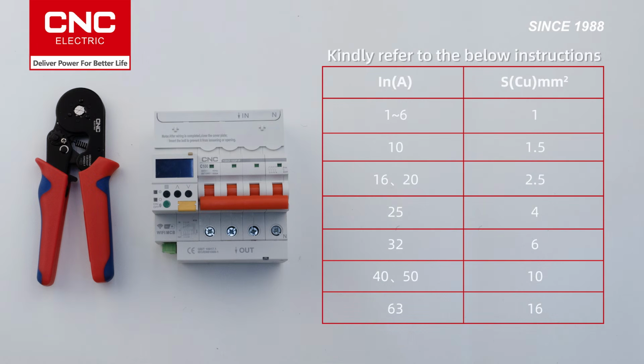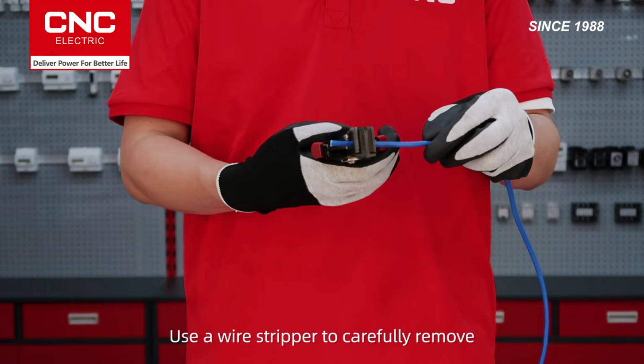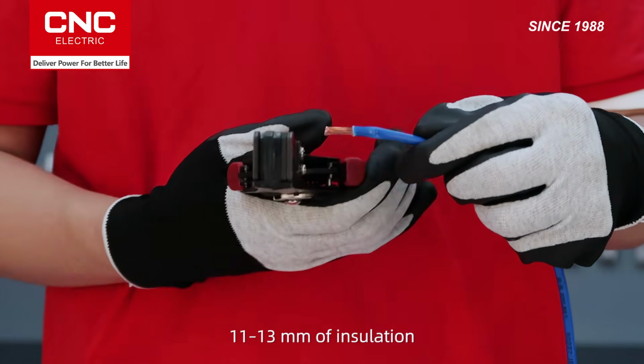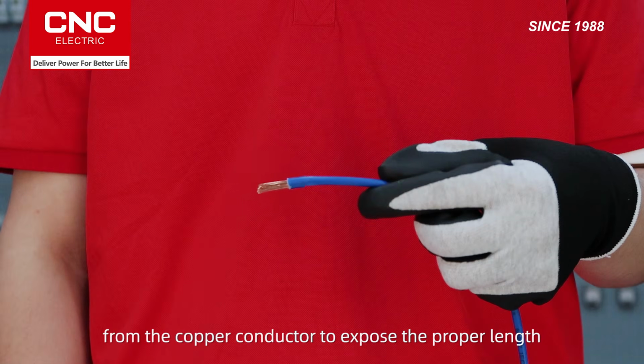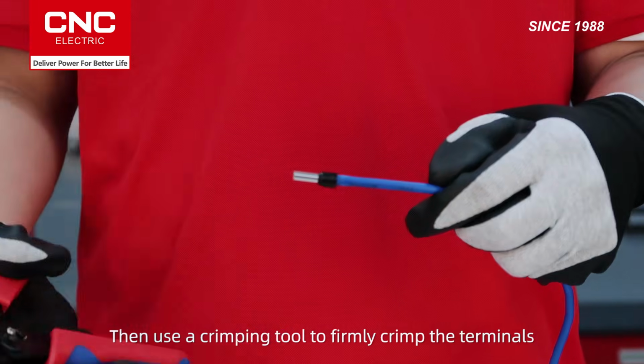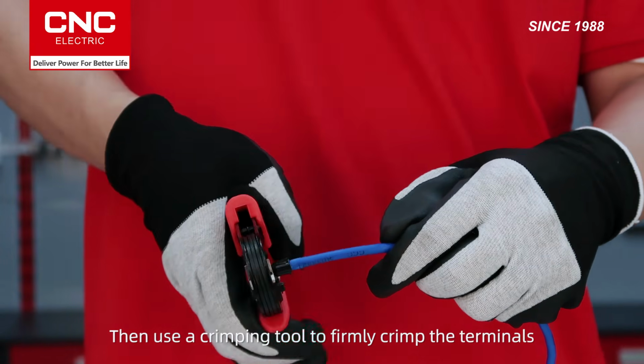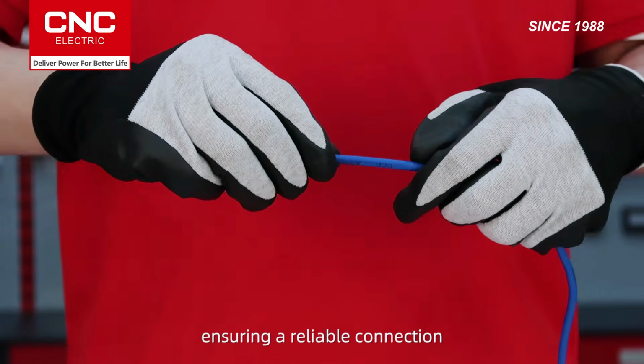Before starting wiring, select wires with appropriate cross sections according to the rated current of the product. Use a wire stripper to carefully remove 11-13 mm of insulation from the copper conductor to expose the proper length. Then use a crimping tool to firmly crimp the terminals, ensuring a reliable connection.